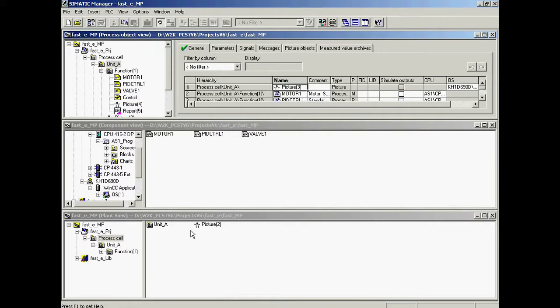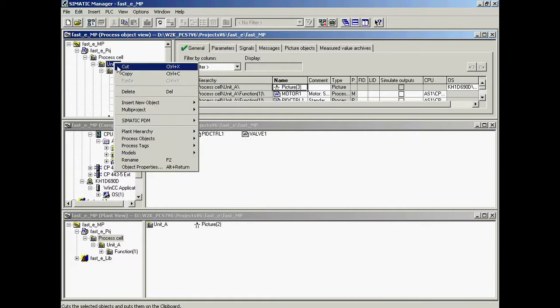With PCS7, it is possible to create a process graphic hierarchy in the OS for operator navigation, which matches the plant hierarchy configured in the controller. The top level in the picture tree hierarchy must correspond to level 2 in the plant hierarchy.